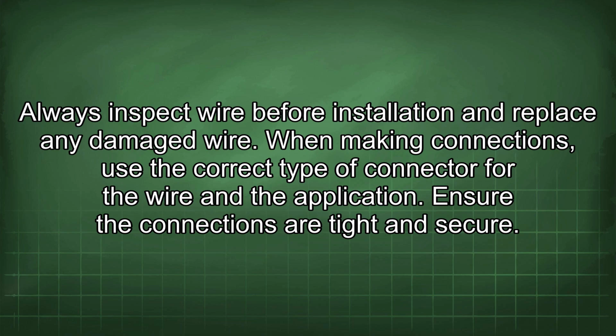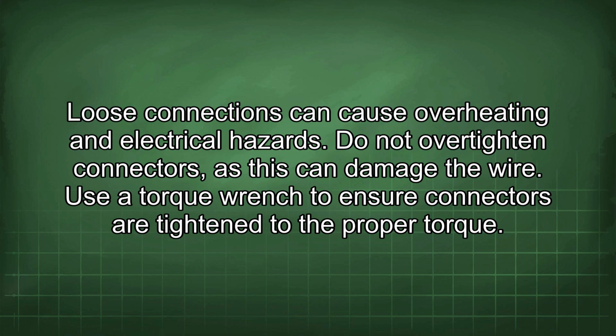When making connections, use the correct type of connector for the wire and the application. Ensure the connections are tight and secure. Loose connections can cause overheating and electrical hazards. Do not over-tighten connectors as this can damage the wire. Use a torque wrench to ensure connectors are tightened to the proper torque.